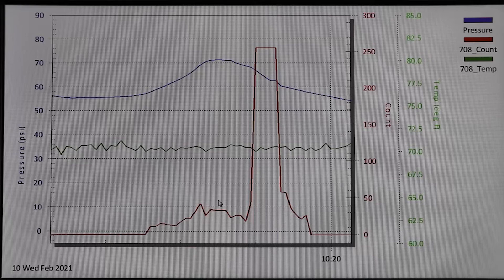In this graph we can see that as system pressure increases the relief valve begins to simmer prior to opening as indicated by the small acoustic signal count. But in this case as system pressure increases the valve opens and attains full lift and remains open until the system pressure drops below its set point where the valve closes almost immediately. In this case no chattering occurred and the valve quickly returned to protecting the system.